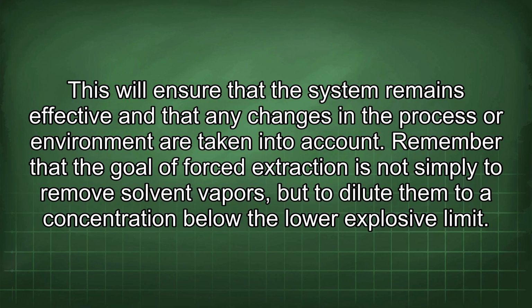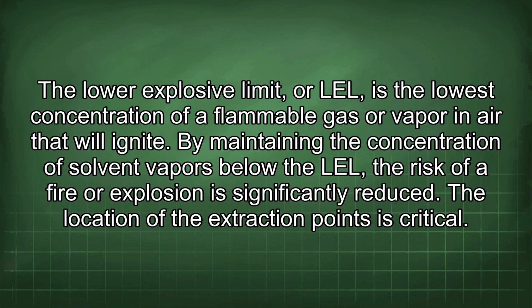Remember that the goal of forced extraction is not simply to remove solvent vapors but to dilute them to a concentration below the lower explosive limit. The lower explosive limit, LEL, is the lowest concentration of a flammable gas or vapor in the air that will ignite. By maintaining the concentration of solvent vapors below the LEL, the risk of a fire or explosion is significantly reduced. The location of the extraction points is critical.